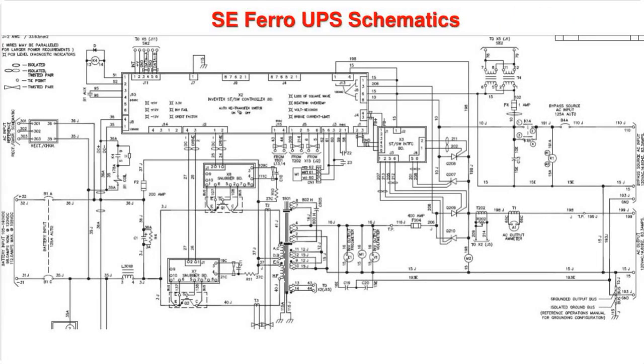So you can see here is our rectifier battery charger, and there's the terminals coming out. That's a positive and that's a negative terminal coming out, and that's connected directly at the positive here and the negative here. Then here's our battery input breaker, and we would connect our battery out at this point here. Okay, so therefore our DC comes into the inverter this way, and you can see we have another choke or inductor in our system here, and we also have some DC capacitors. That smooths out the output from the charger even more, to make sure that the voltage going to the battery is nice and smooth and doesn't have any spikes on it.